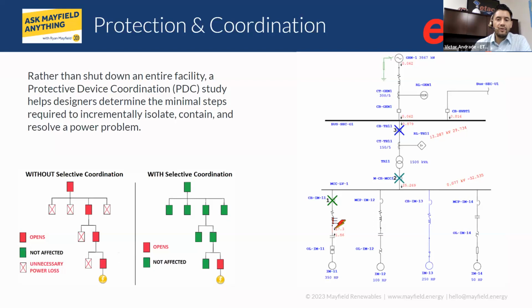In a software or platform like ETAP, this is done graphically. So Nick is going to be going over a little bit more on the behind the scenes, the time characteristic curve, how it's performed. But the software does give you the ability to simulate a fault. So you could, for example, see there's an animation going on. There's a lightning bolt in red that is placed between a motor and a conductor, and you could see that number one starts to flash. That's the first protective device that would trip.